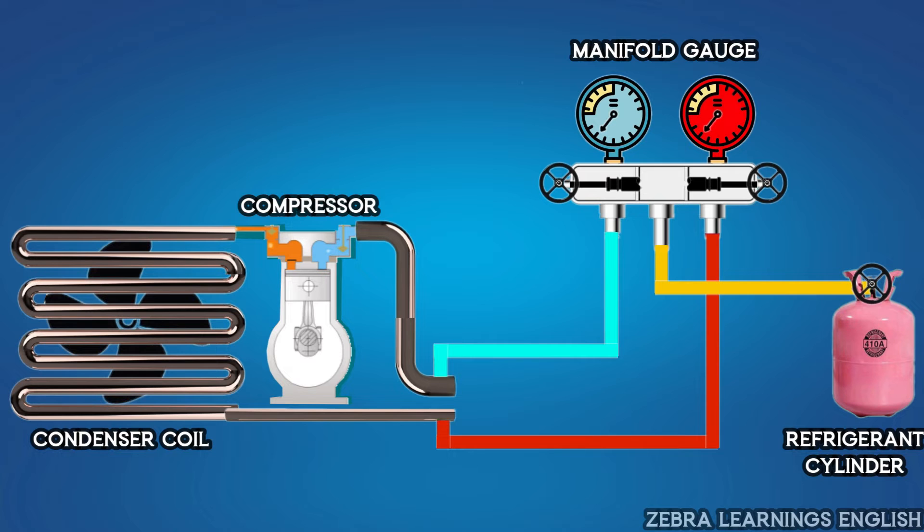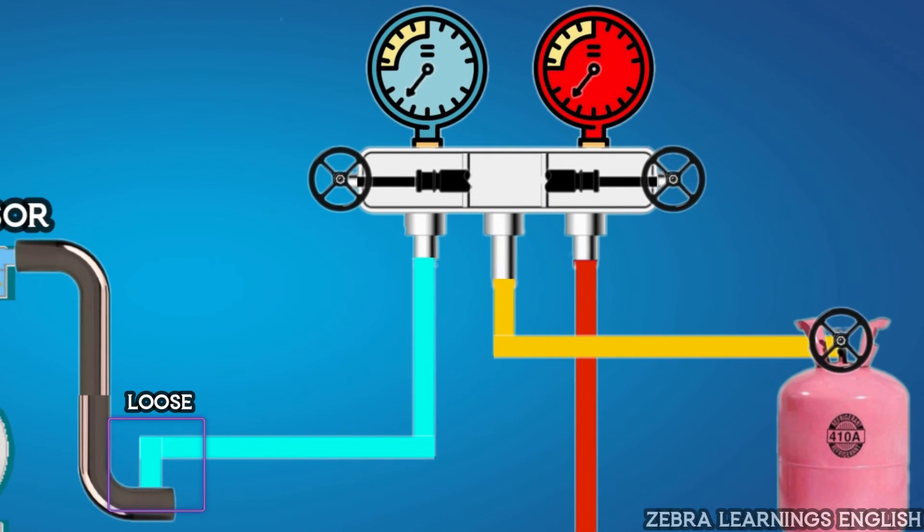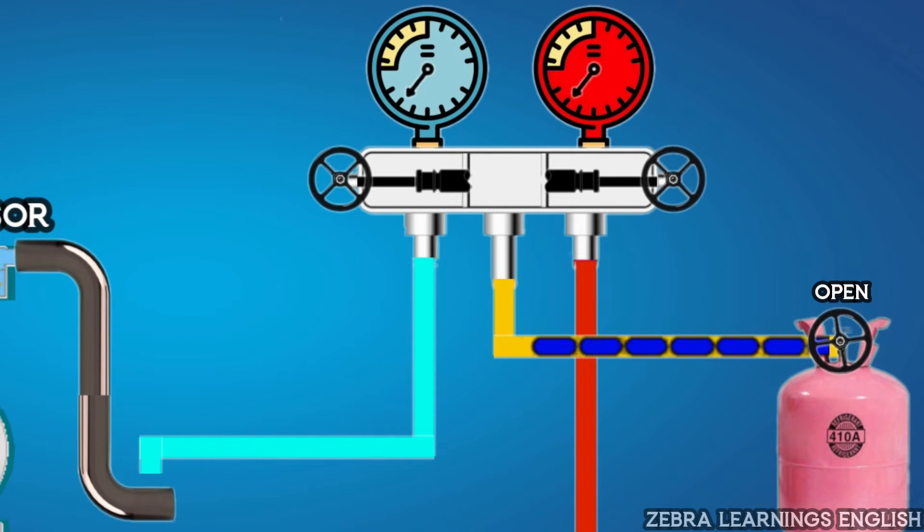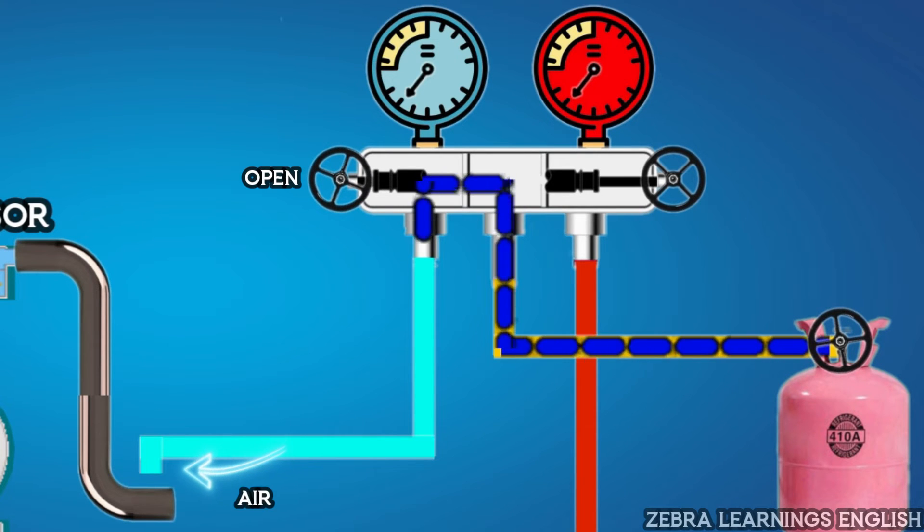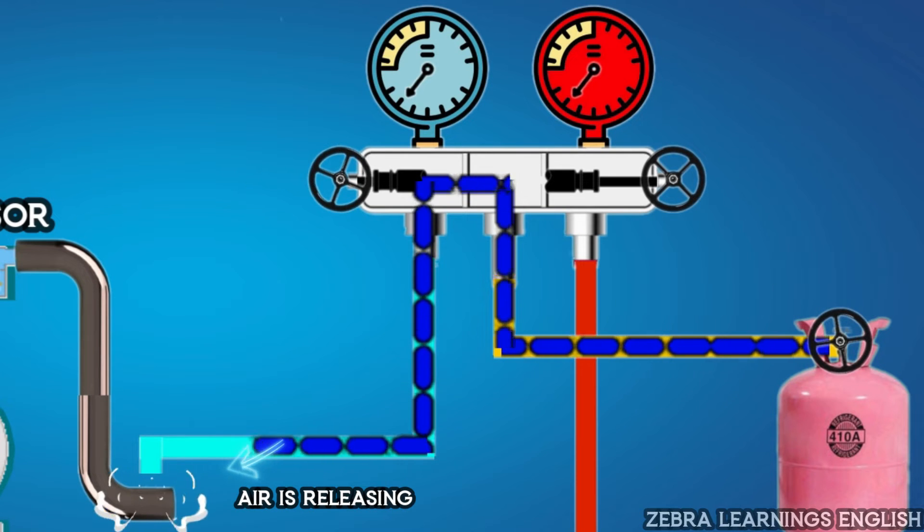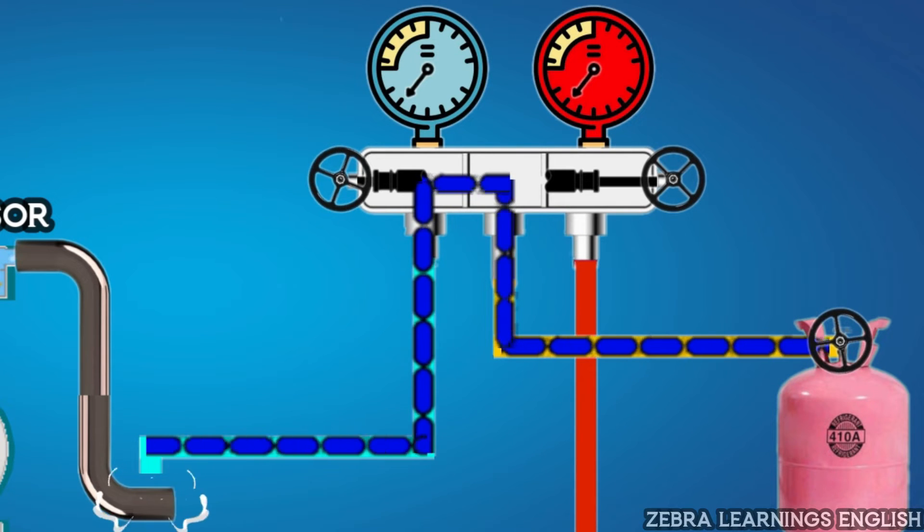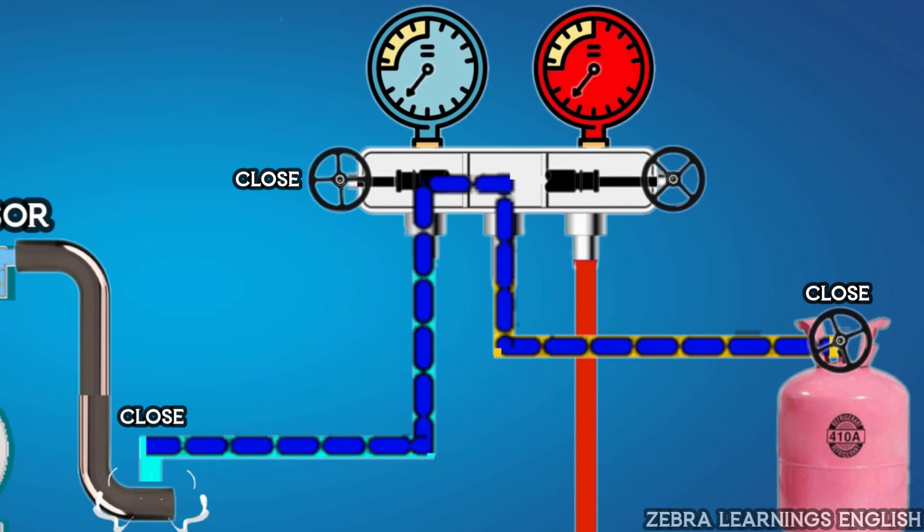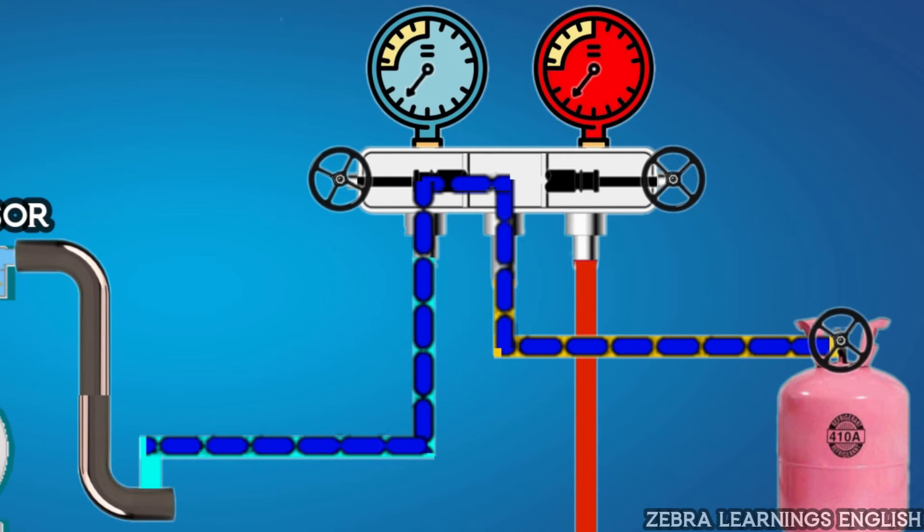Now, loosen the low-pressure hose a little from the charging port. Then, open the refrigerant cylinder and then open the low-pressure on-off valve. Now, the refrigerant is leaking through the low-pressure hose. By doing this, the air inside the hose will escape. Now, tighten the low-pressure hose in the charging port and close the cylinder and on-off valve.